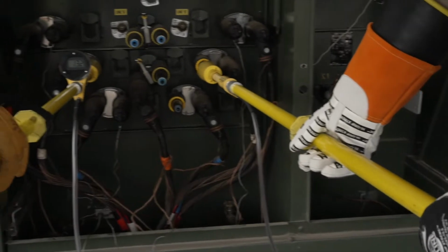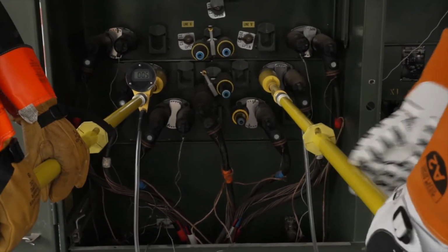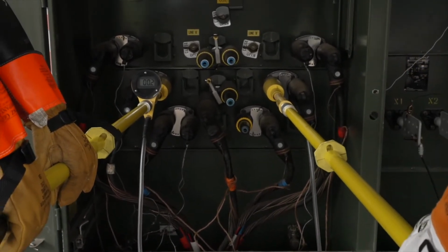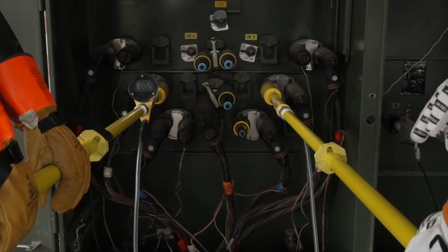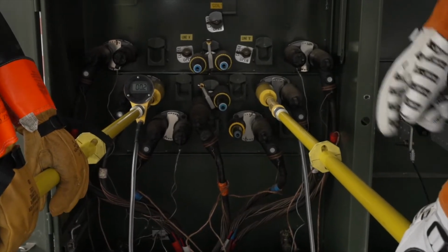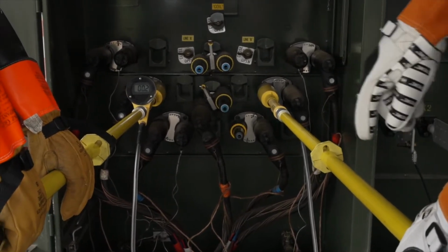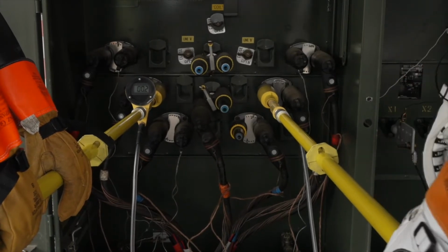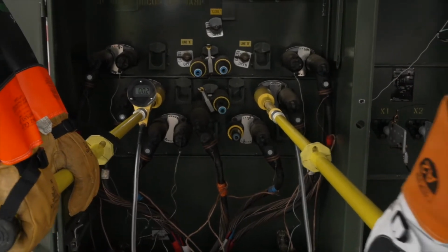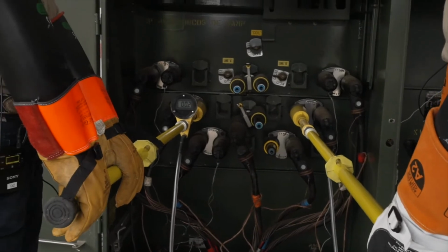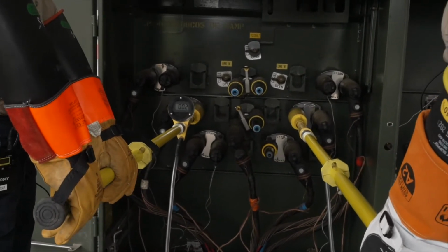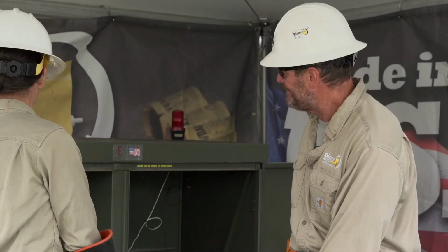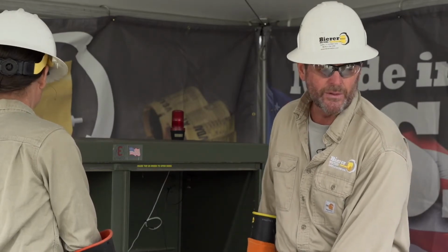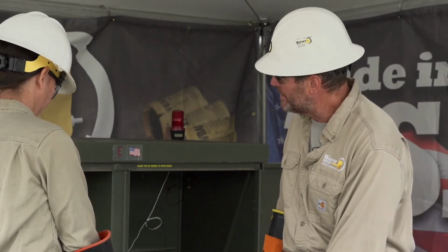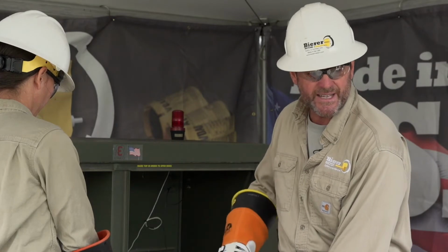What you got? 0.2. All right, so we got a little bleed in that cord. This cord, because it's shielded, you can use it with it laying on the ground. If we were on wet grass, it would probably be reading a 0.5 or 0.6 - it'd be a little higher, because there'd be more bleed to ground through the wet grass. So we know the cord is safe, but we're staying away from it.